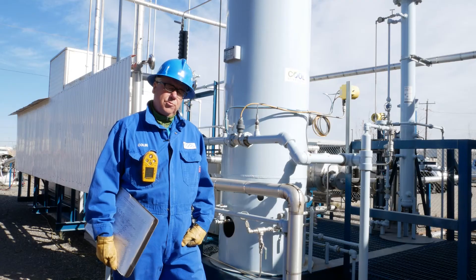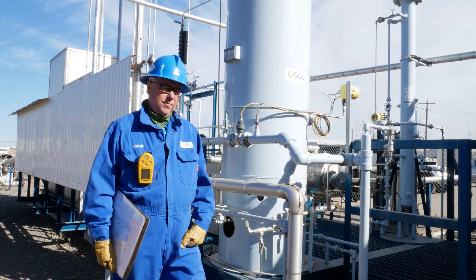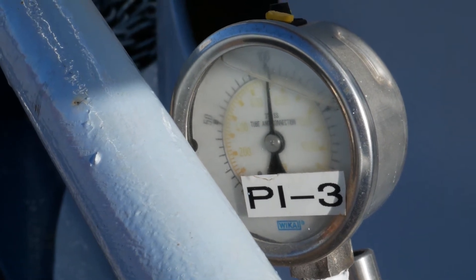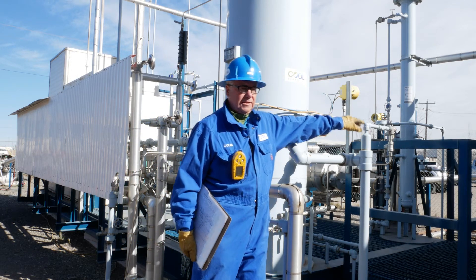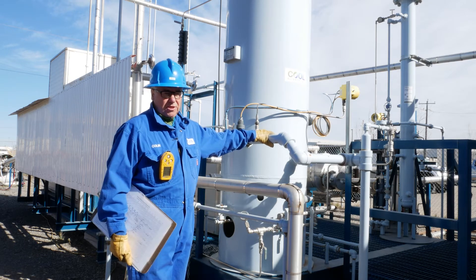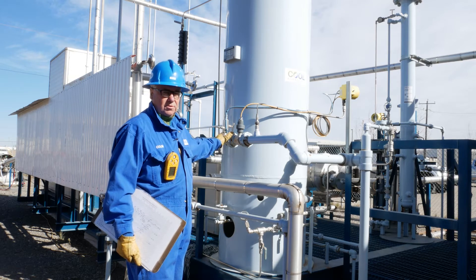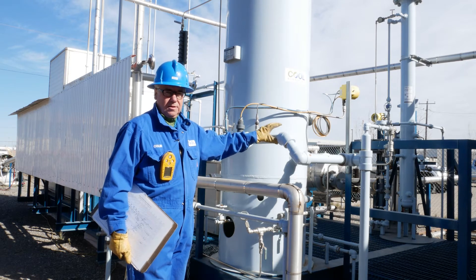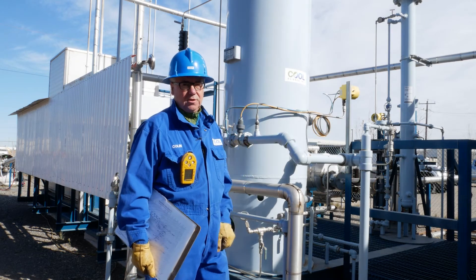It re-vaporizes the liquefied natural gas back into a vapour, and there's a red line feeding into the pilot facility to then re-liquefy that methane again. So we're at the point in our plant where we reintroduce the gas. The red line from the fuel tank is feeding the gas here at 100 psi. There's a regulator which drops pressure down to about 15 psi and is fed into the system — that's the make-up gas. This other line is the methane that wasn't turned into LNG; it was cold vapor inside the cold box. The cold is recovered through two gas-gas heat exchangers, comes out of the box warmed up, and is now the recycle gas heading over to the compressor.